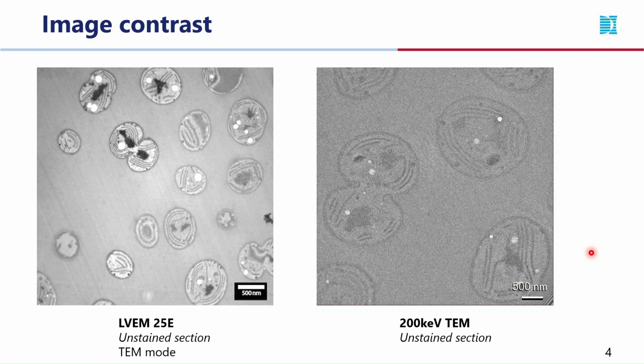The explanation for this property can be found directly in physics, since slow electrons are much more scattered than fast ones, which pass almost unnoticed by the sample. On the contrary, the slow ones have much more time to collect the information from the sample. A direct consequence of this property is that we can reduce or even eliminate the staining, and even without staining, we reach comparable results as in the case of conventional instruments with stained samples.